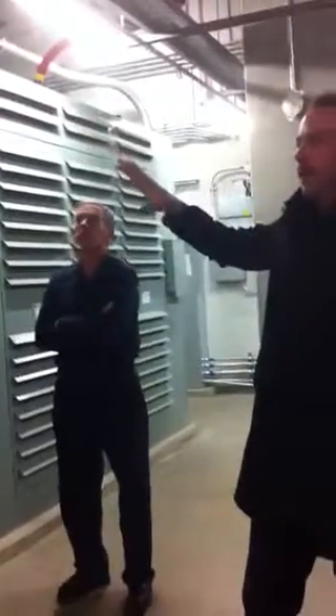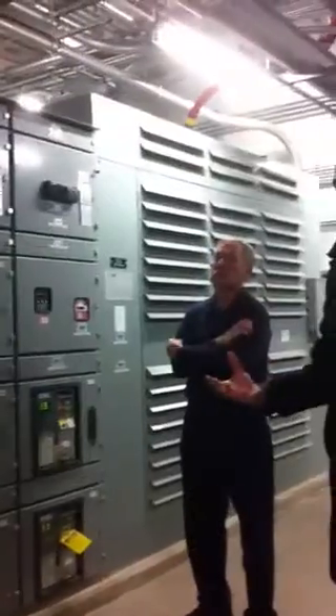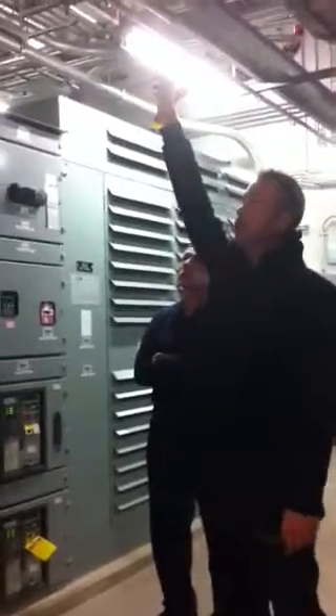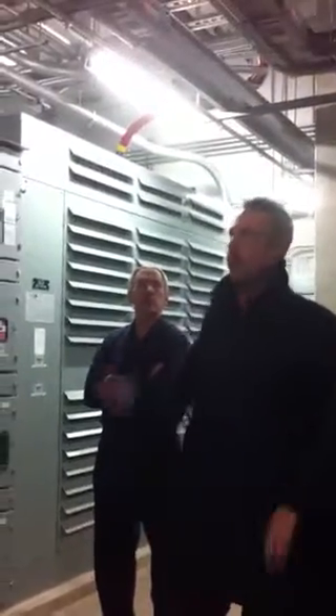So the distribution in the building, you'll notice there's different ways of feeding boards. You'll notice the high voltage primary cable, which is the red stuff, is Teck cable. You'll notice pipe work coming out of the back, which is wire and conduit. And then you'll notice these two runs right here, which is a bus duct system. These bus ducts run out of the main board, each from their own breaker, and up the riser east and up the riser west. From each one of those bus ducts, we tap off and feed a 600 volt distribution board similar to one of these.